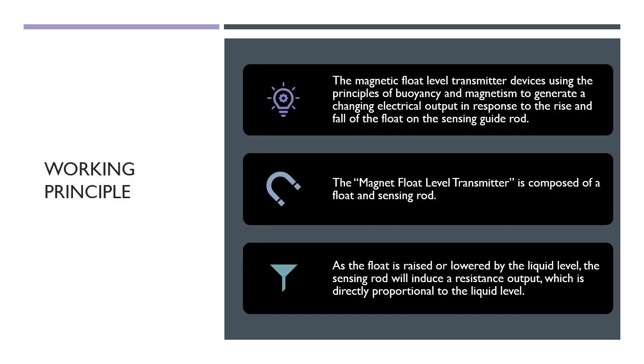Continuing with the working principle: the magnetic float level transmitter uses the principle of buoyancy and magnetism to generate a changing electrical output in response to the rise and fall of the float along the sensing guide rod. This device is composed of a float and a sensing rod. As the float is raised and lowered by the liquid level, the sensing rod induces a resistance output directly proportional to the liquid level.